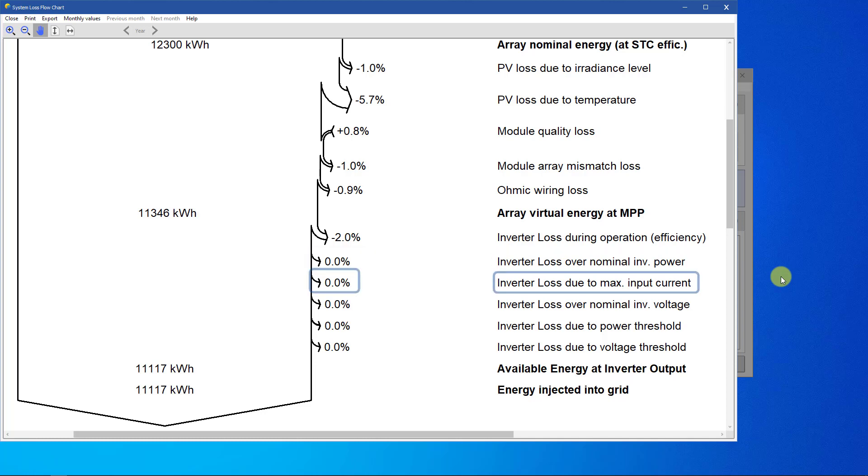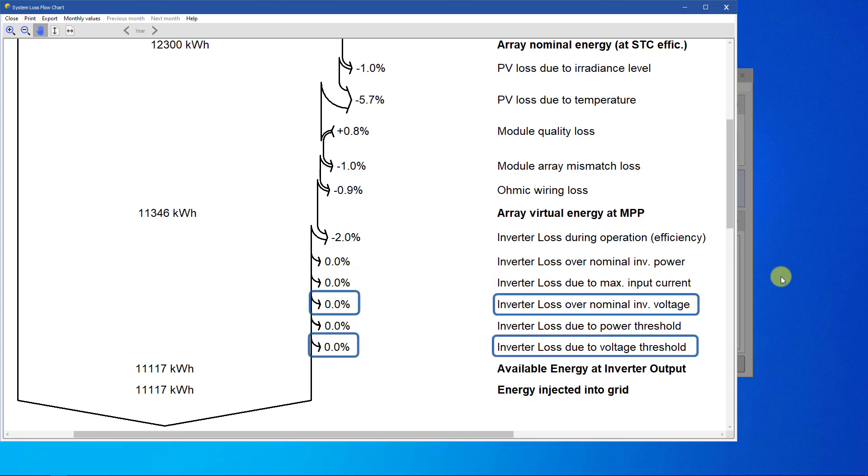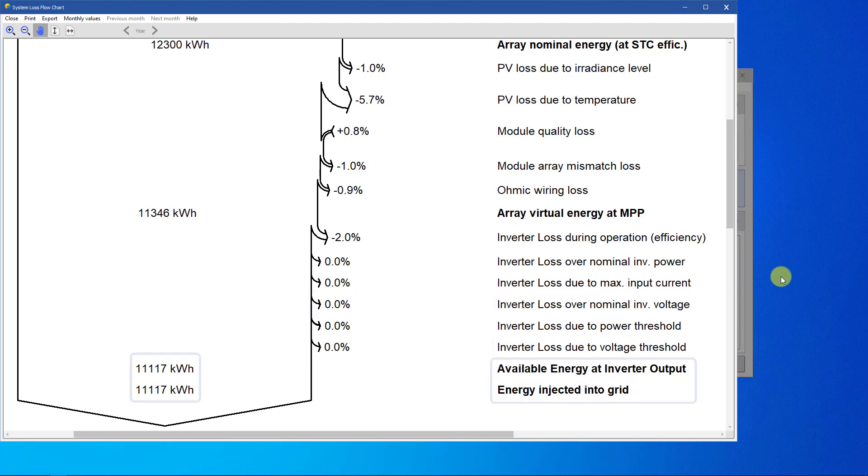You can sometimes see limiting losses due to maximum input current. The losses over nominal input voltage and due to voltage threshold are usually null. A significant value indicates that the sizing is not correct. You have too many or too few modules in series relative to the inverter. In absence of losses in the AC circuit after the inverter, the energy at the output of the inverter is equal to the produced energy injected to the grid.